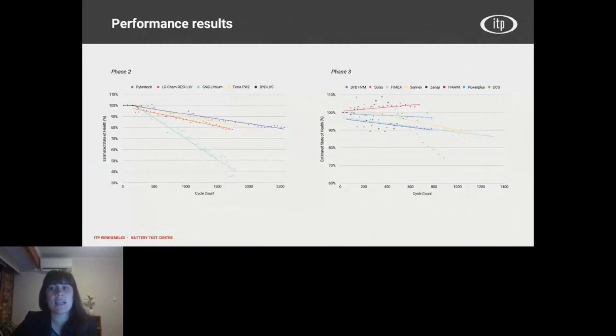We'll discharge at a lower 4-hour rate and a temperature of 25 degrees Celsius. You can see here the latest capacity test up to this month for the remaining phase 2 and phase 3 batteries. Just be aware of those different scales on the y-axis. You'll see there's a fair amount of variation in capacity, not only between batteries, but also between tests for the same battery.